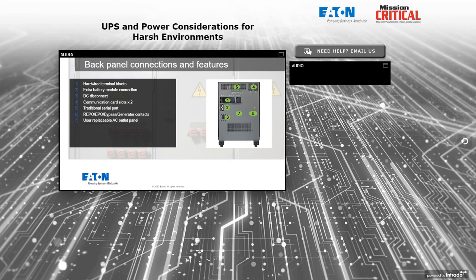Communication card slots. This is something that in the older days was not really considered beyond just an RS-232 port. For an industrial UPS today, communication is very important, and the security of that communication is paramount. So I'm not just looking for a communication card necessarily, but one that has passed the stringent UL or IEC requirements for communication security. An additional serial port, however, is often still included because in many applications, that's still the kind of communications that they use. But by itself, that's usually not enough for a new installation. The ability to do remote emergency power off, front panel emergency power off, contacts to tell whether the generator is feeding the UPS or the utility is feeding the UPS, terminal blocks to accept that information, typically by dry contact as opposed to an analog signal level.